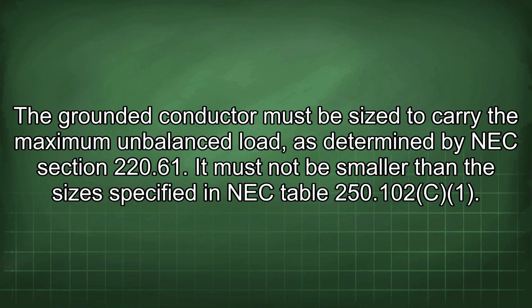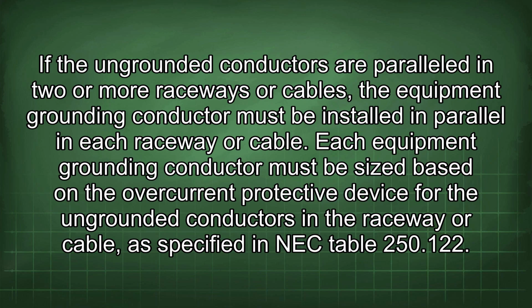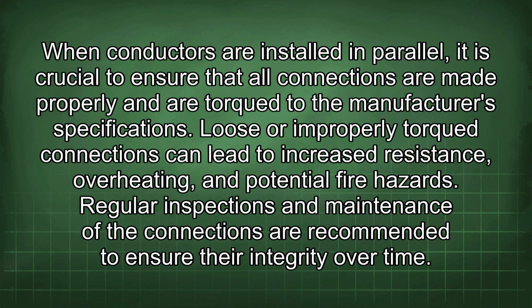250.102(C). If the ungrounded conductors are paralleled in 2 or more raceways or cables, the equipment grounding conductor must be installed in parallel in each raceway or cable. Each equipment grounding conductor must be sized based on the overcurrent protective device ahead of the conductors in the raceway or cable, as specified in NEC Table 250.122.